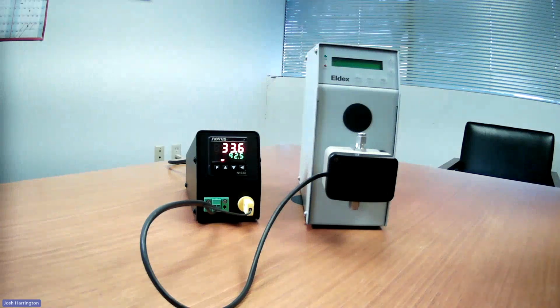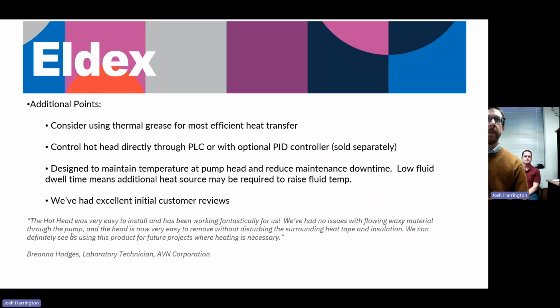Now this will take between 5 and 10 minutes to heat up typically. Maybe a bit longer if you're actually pumping fluid at the same time, but it's very rapid to increase the temperature, and then it's incredibly stable at that point. A couple other points just to mention, back to the presentation, we have found that using some type of a thermal grease on the inside of the aluminum between the device and the pump head can help with the efficiency of heat transfer. Just to note, that is a little bit messy sometimes, but it does reduce the heating time and improve the overall efficiency.